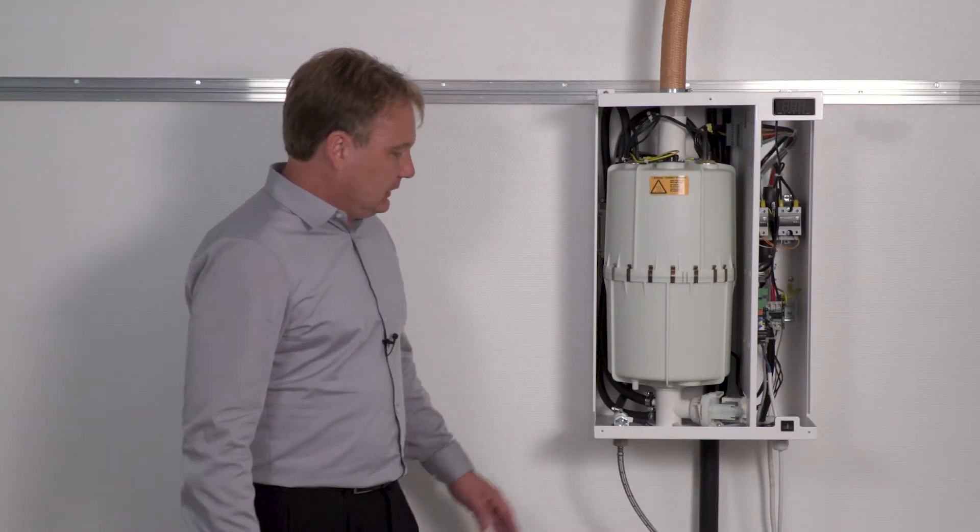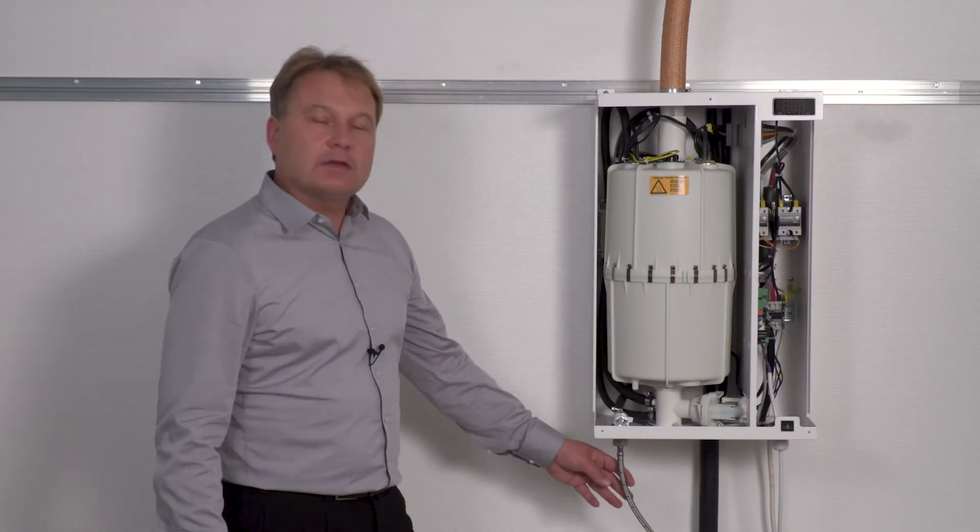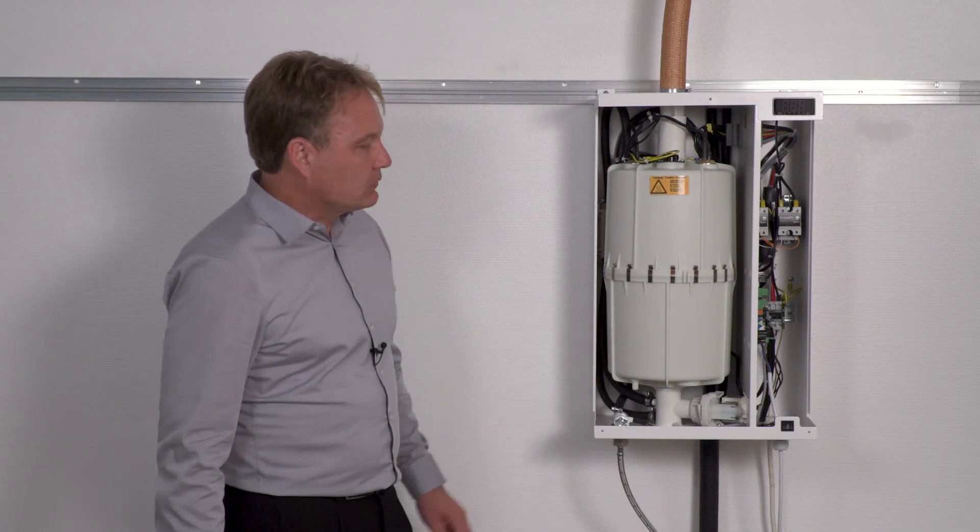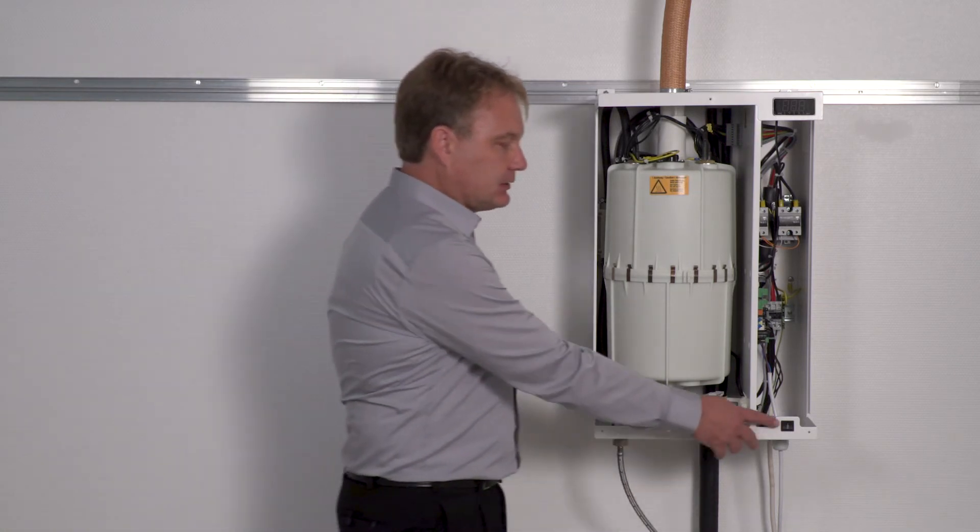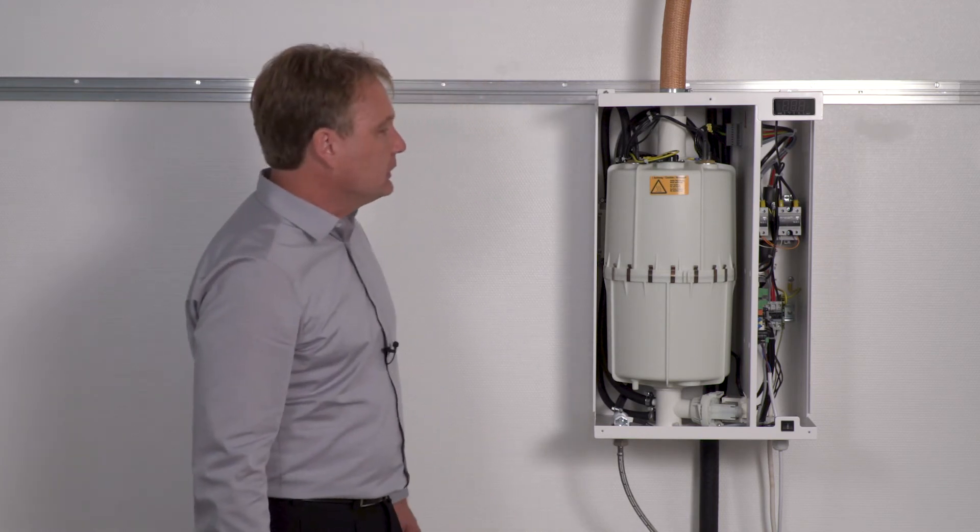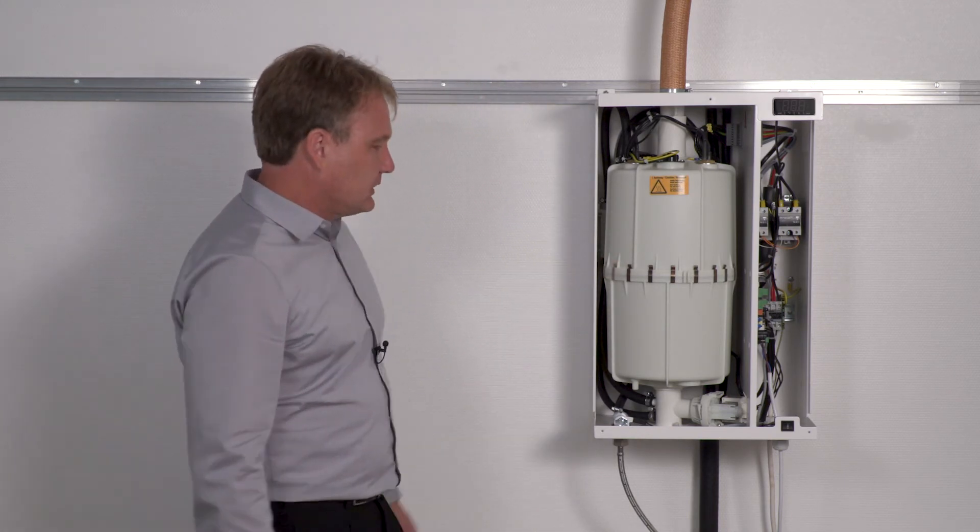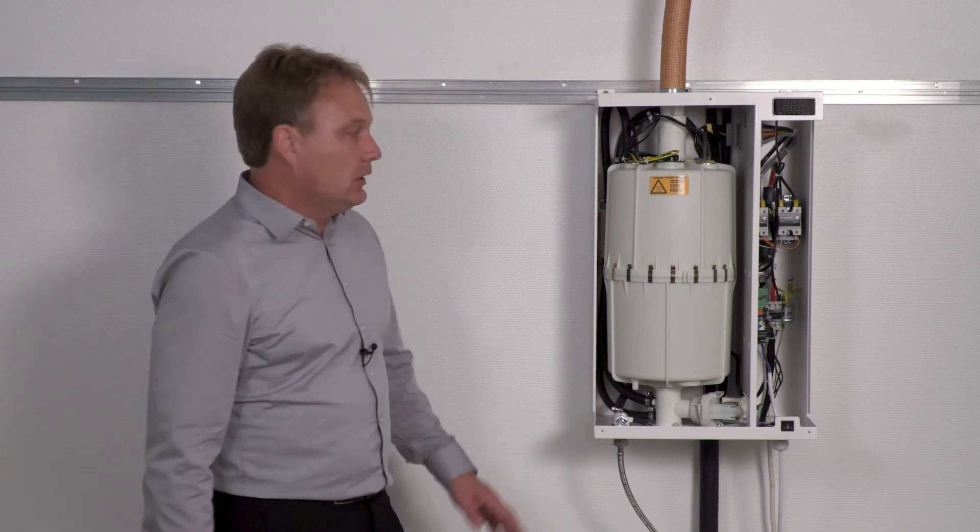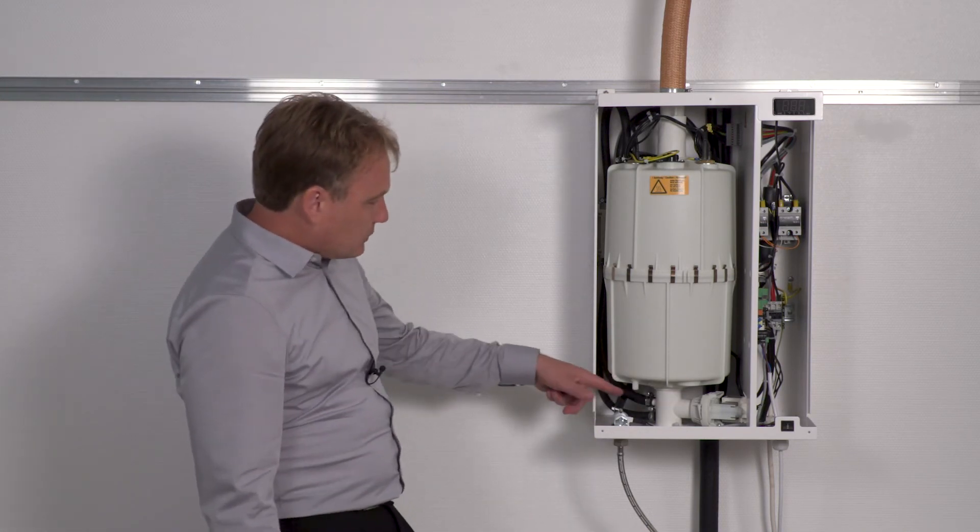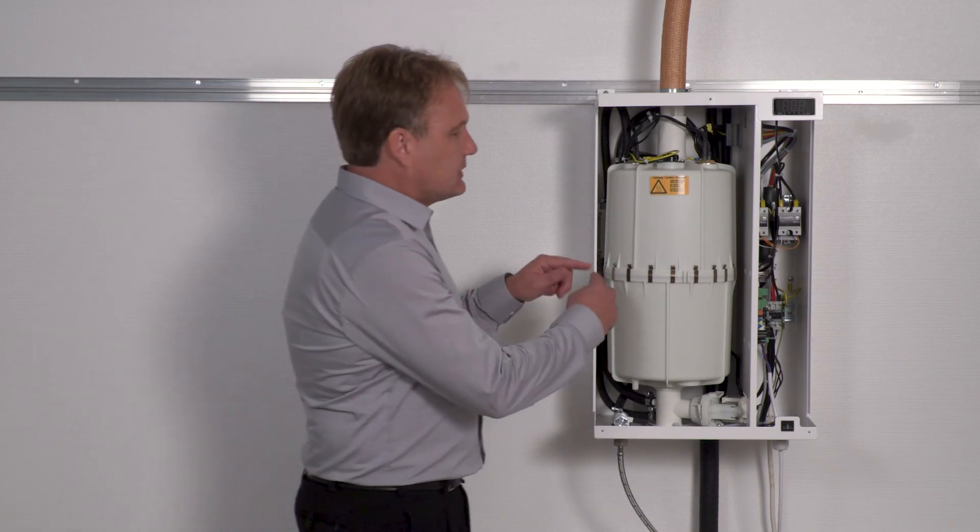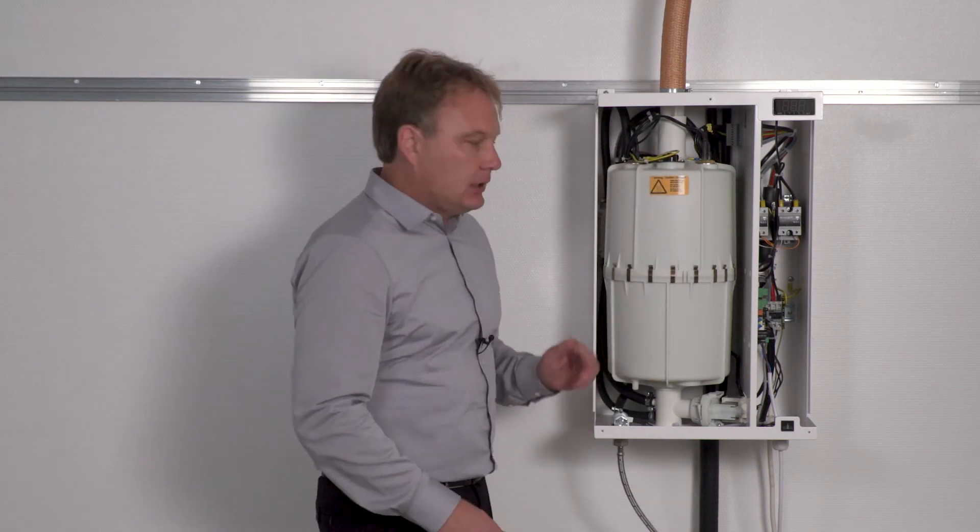Now I can start a test run. I have turned the water back on and the power as well. Now I switch on the unit by pressing the control switch to position one. Let the unit run for about 10 to 15 minutes at full steam production and check especially around the hose clamps, around the replaced O-rings, for leaks or leakages.